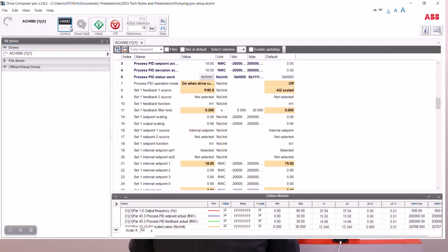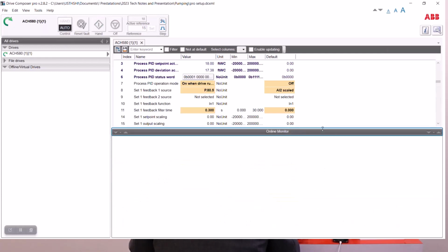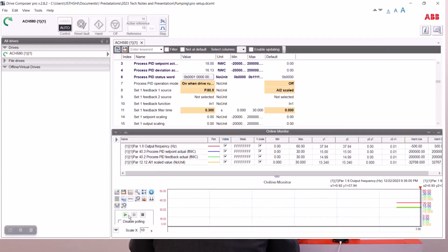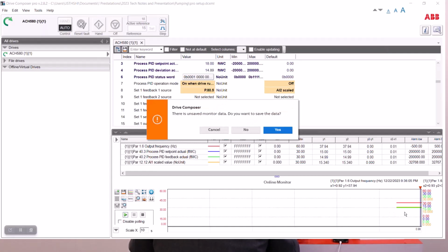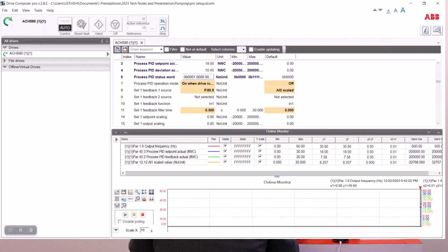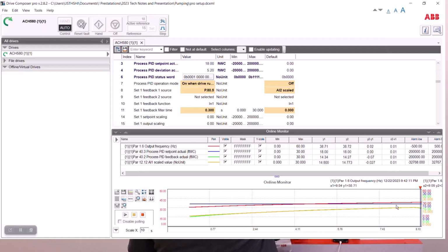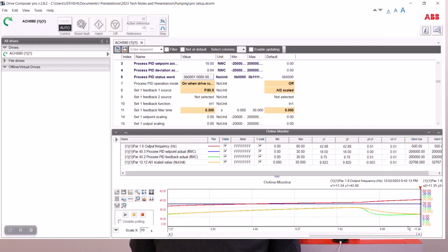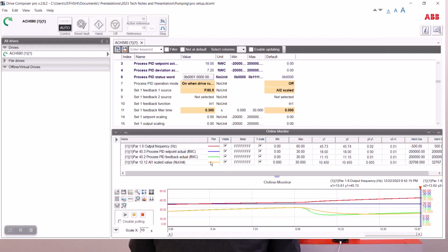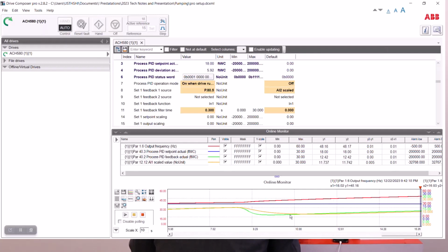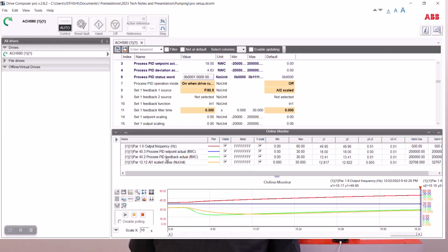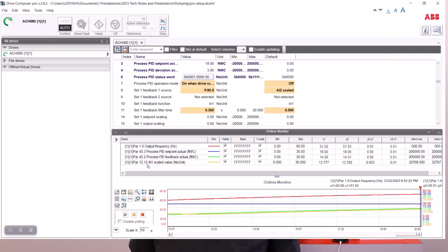So I'm going to start the drive. I'm going to put it in auto mode, and that's going to start the drive. And what I'm doing is I'm going to turn around and start the graphing right here. So what's happening is I've started the drive already, and the drive right now, in red, that's the speed of the drive's output, and it's bringing up the speed right now. And in green and orange here, we are looking at our PID feedback actual and our AI1 scaled.